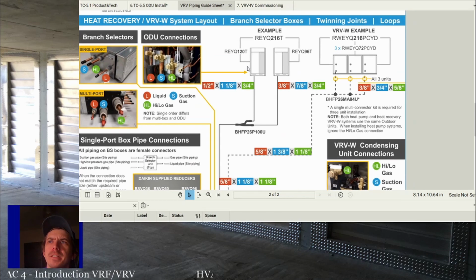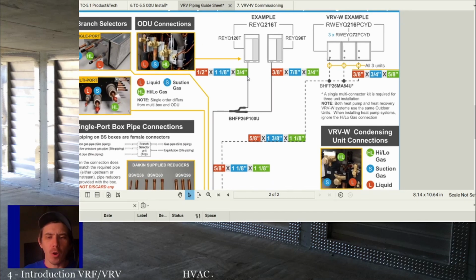I don't have any slides pulled up on it, but let's talk wiring real quick before we talk about commissioning. Wiring is easy, easy, easy when it comes to VRF. Here are the basic rules that apply to all manufacturers when wiring VRF. You're always going to need 2 wires. Very rarely are you going to need more than 2 wires for communication. We're not talking power here.